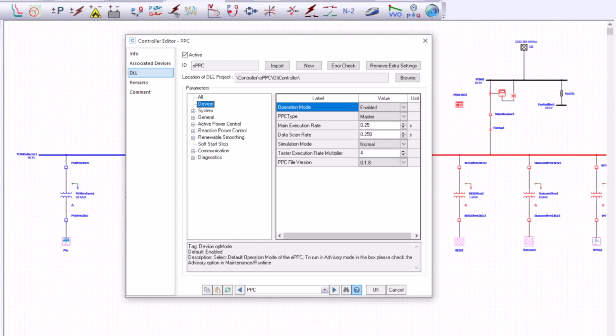ETAP is capable of operating as a real-time simulator, which means that it can continuously exchange live measurement and control commands with the deployed EPPC hardware. This feature is particularly useful for validating system behavior before deployment in the field and allows us to test and fine-tune the control logic in a safe, simulation-based environment.